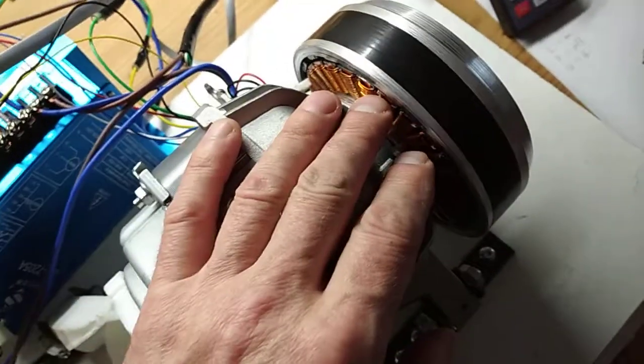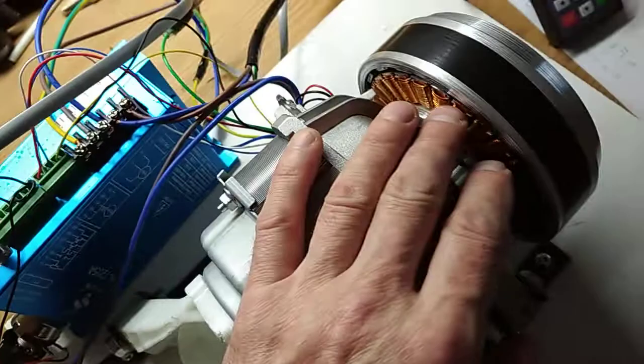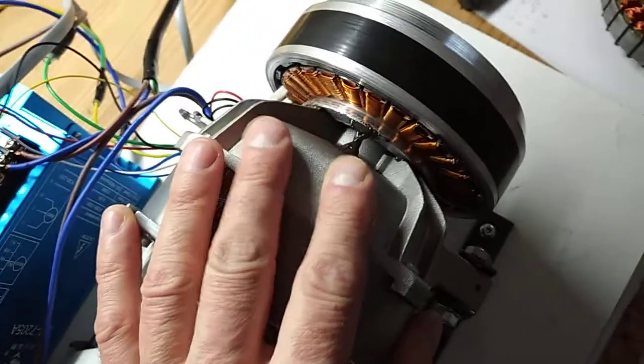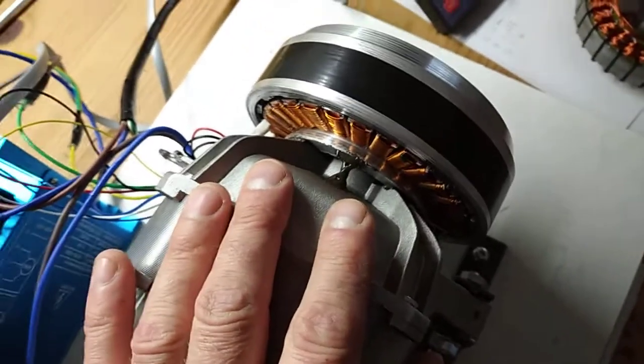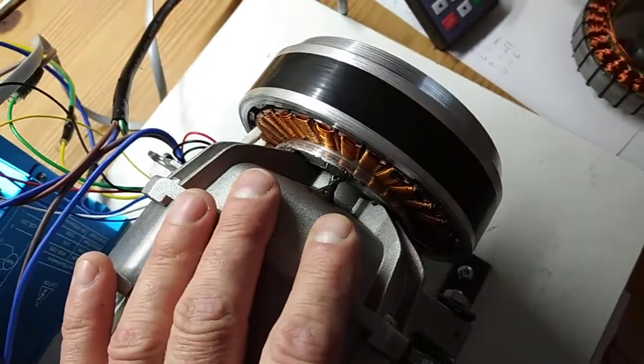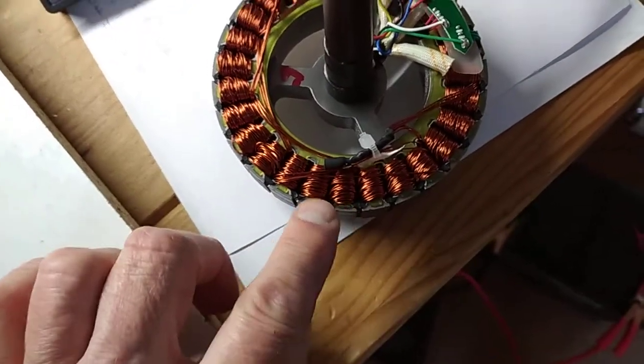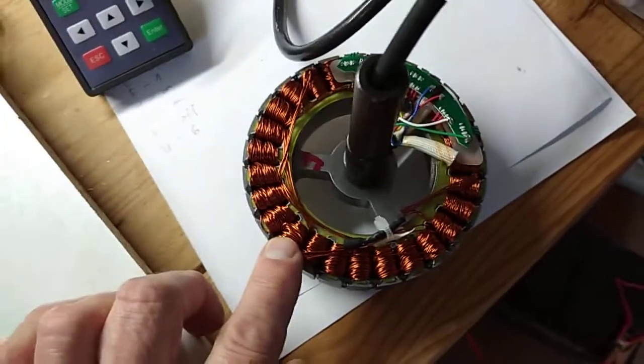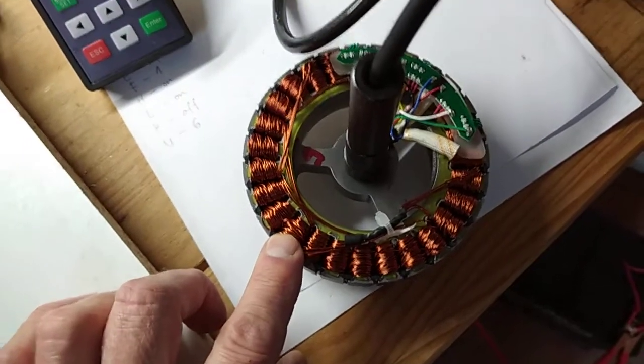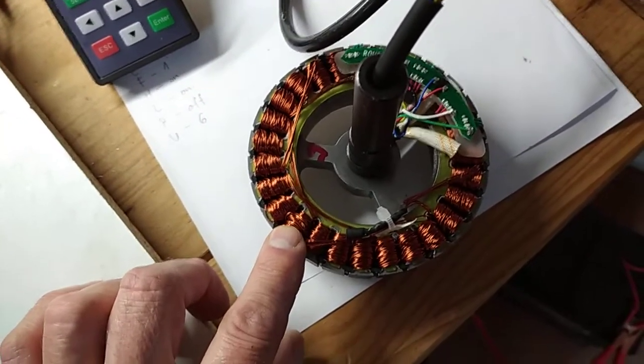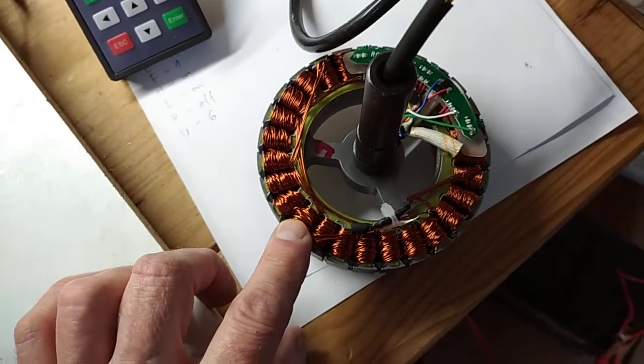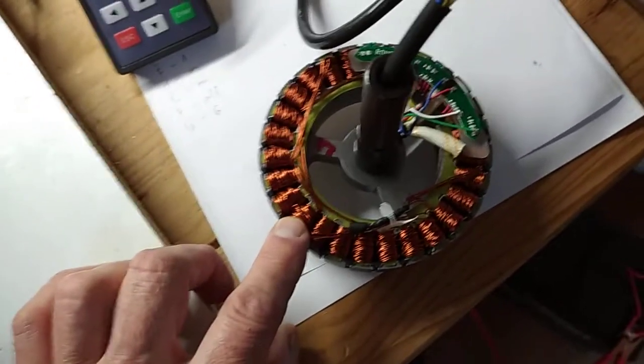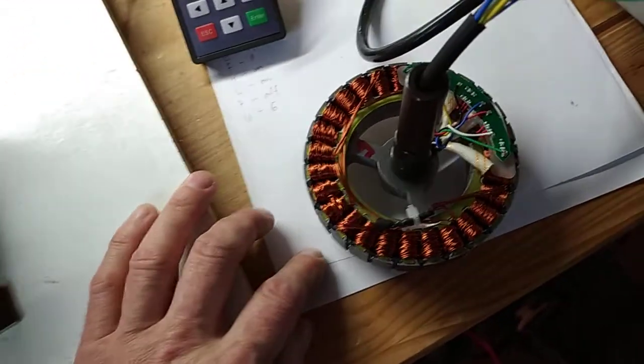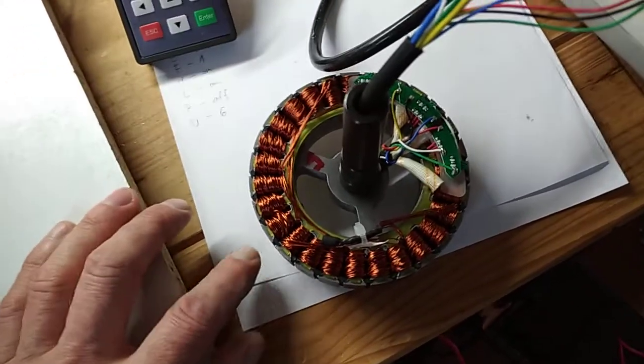This is not the greatest motor for the driver, because I believe this is a 9-pole motor. Why do I say I believe? There are 27 poles that have been rewound into 3-phase. So 27 divided by 3 phases is 9 poles. But again, if you have better information about how to calculate poles, that would be great.